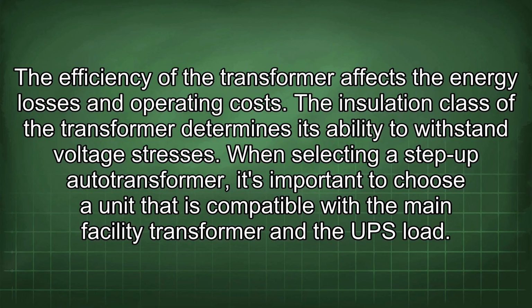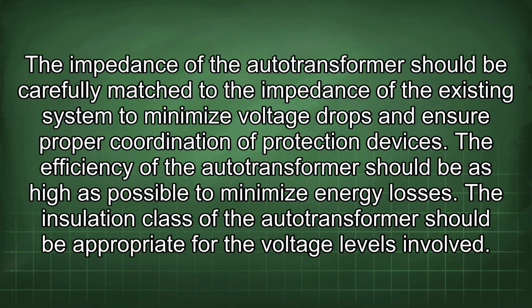When selecting a step-up autotransformer, it's important to choose a unit that is compatible with the main facility transformer and the UPS load. The impedance of the autotransformer should be carefully matched to the impedance of the existing system to minimize voltage drops and ensure proper coordination of protection devices. The efficiency of the autotransformer should be as high as possible to minimize energy losses. The insulation class of the autotransformer should be appropriate for the voltage levels involved.